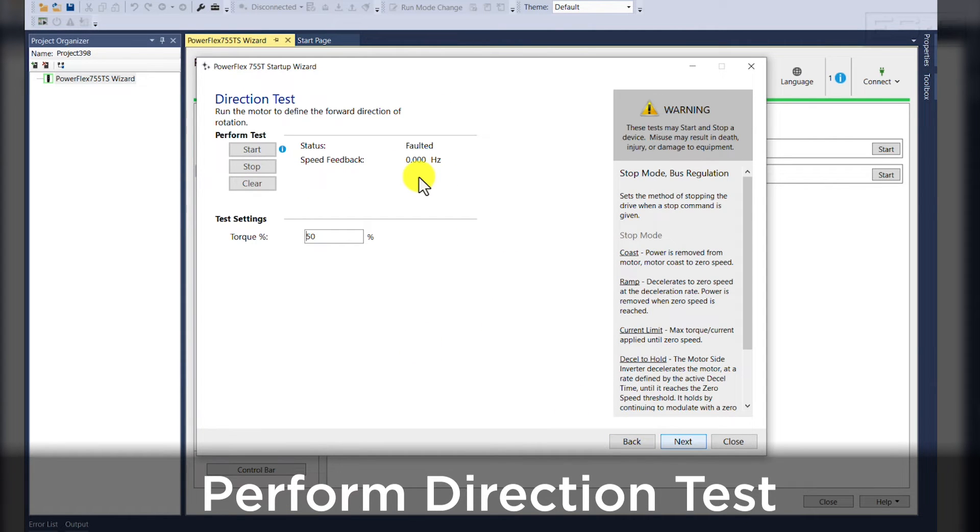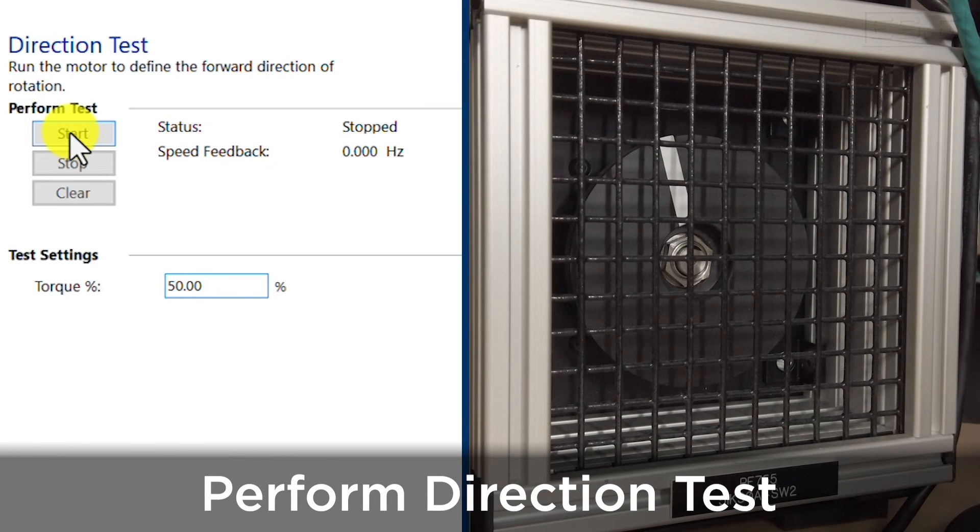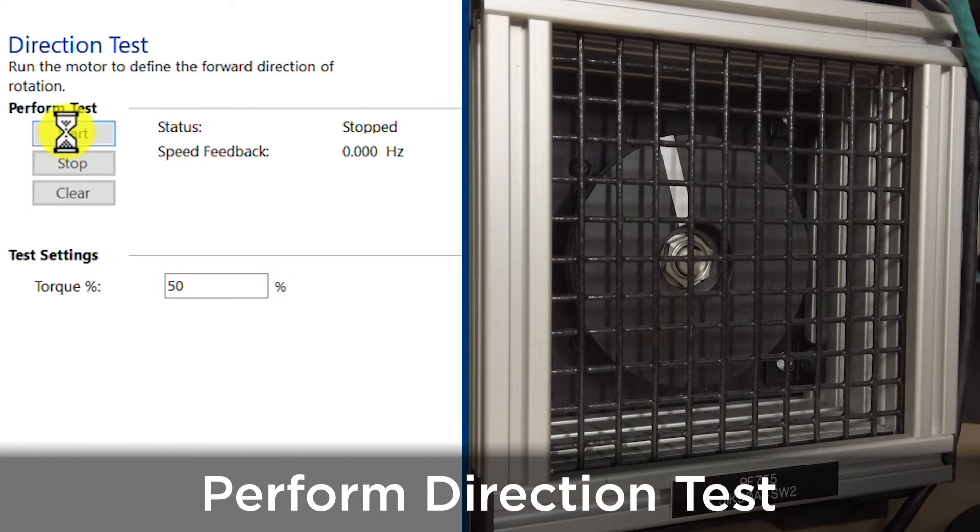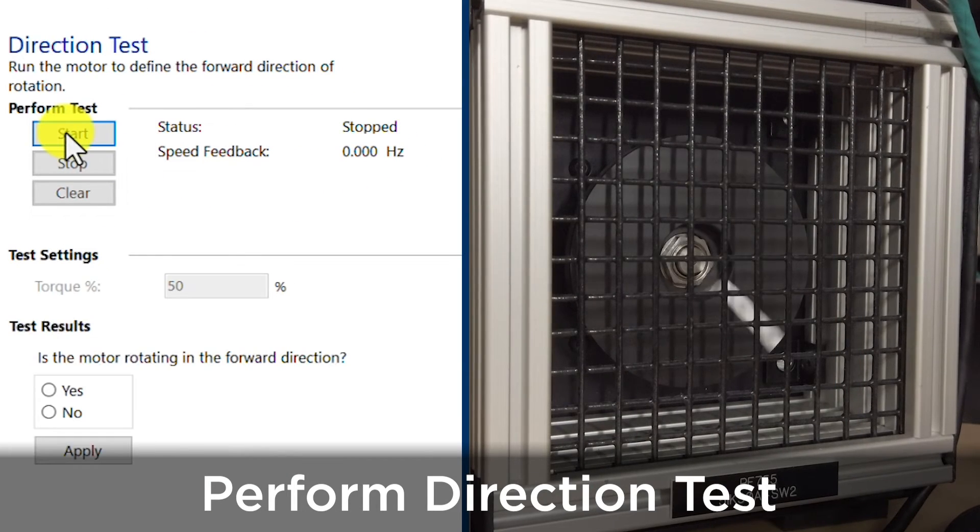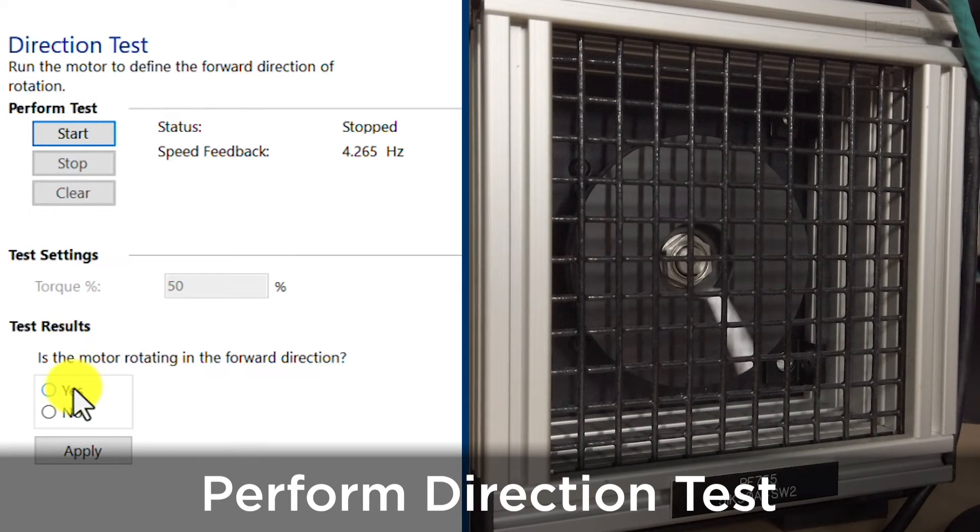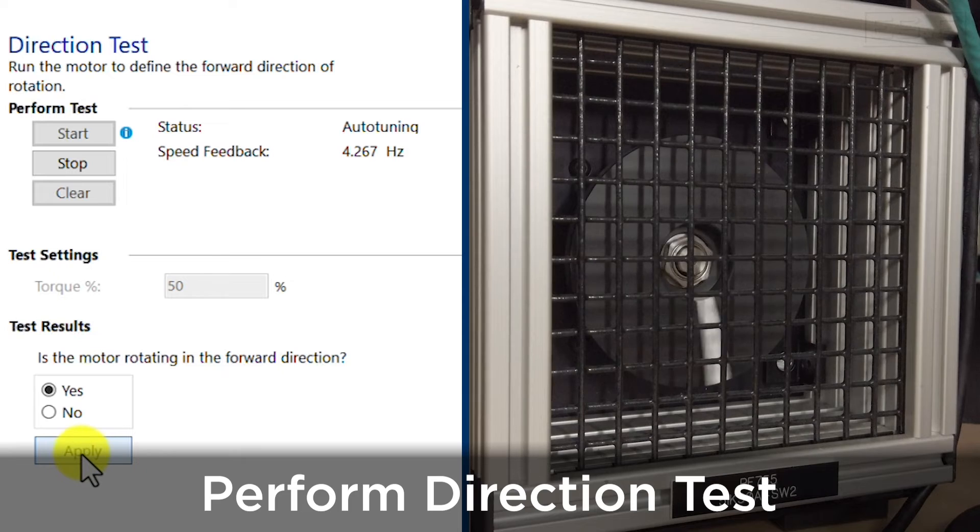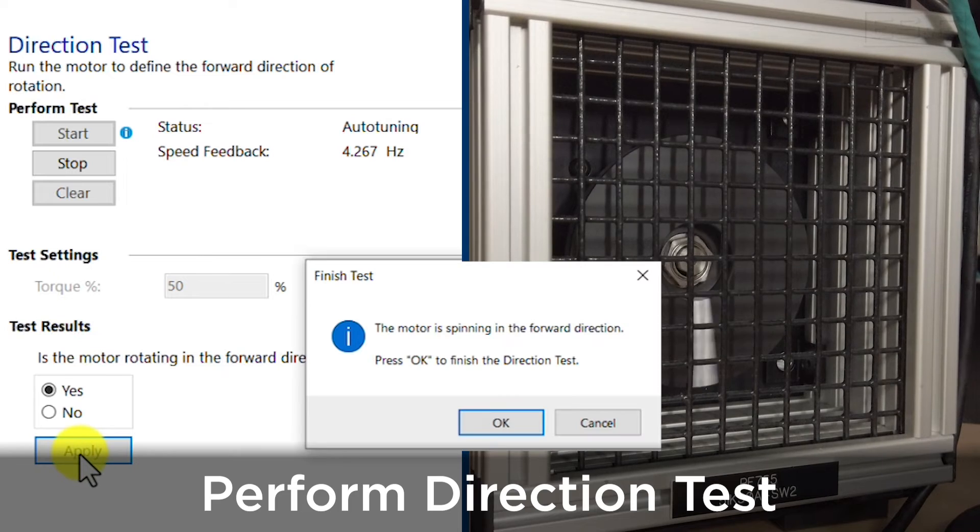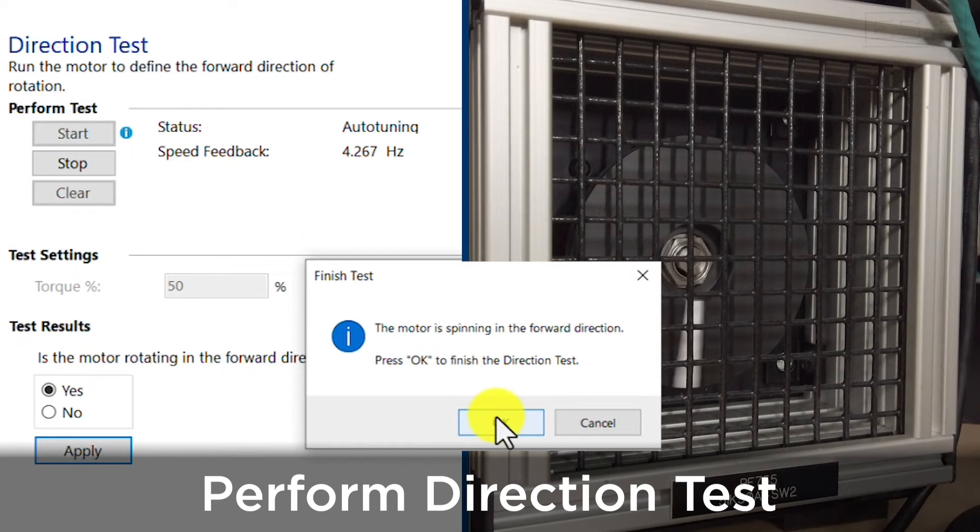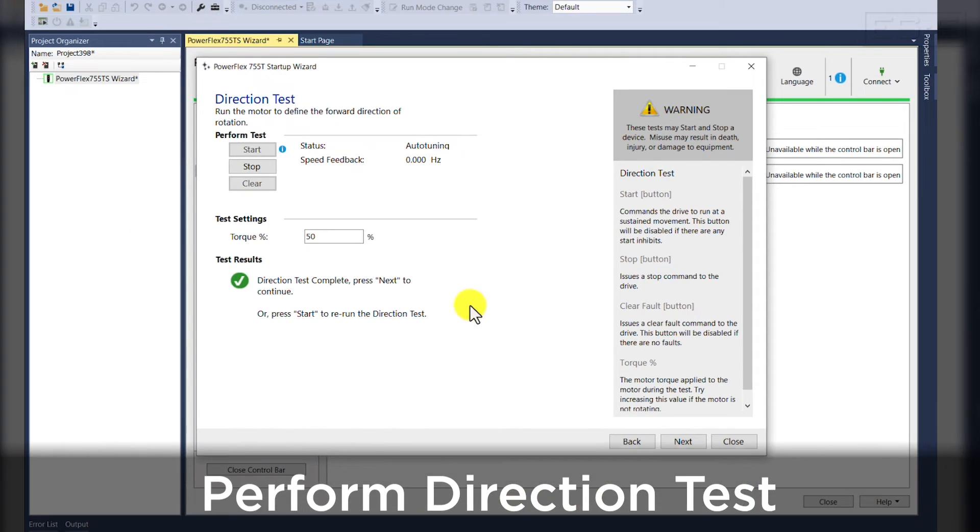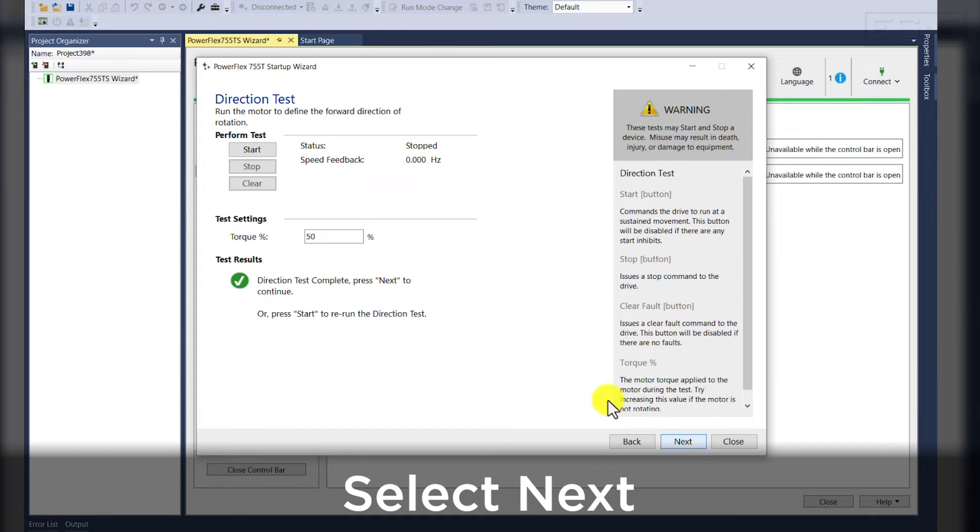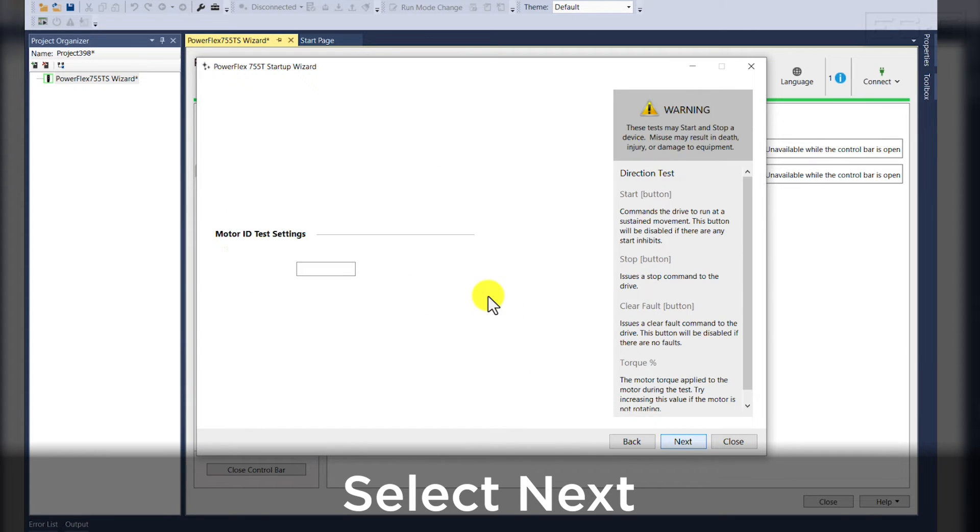Then we're prompted to perform a direction test. Once you hit start, your motor should operate and we see that our motor is rotating in the forward direction. So we'll hit yes and apply and okay to finish the direction test. Now that our direction test is complete, we'll hit next.